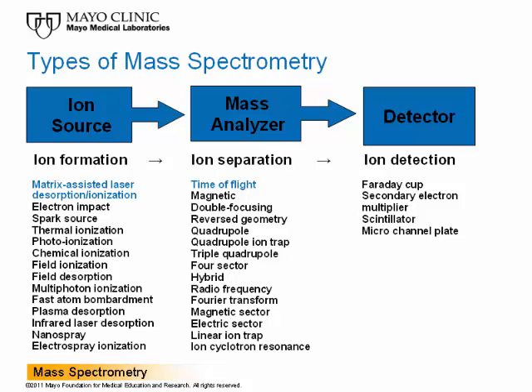Matrix-assisted laser desorption ionization is a soft ionization technique, allowing molecules to remain relatively intact during ionization. Proteins can be measured as little protein fragmentation occurs. Following ionization, the ions are separated, enabling measurement of mass. Using the approach covered in today's presentation, ions are separated by time of flight in a flight tube.